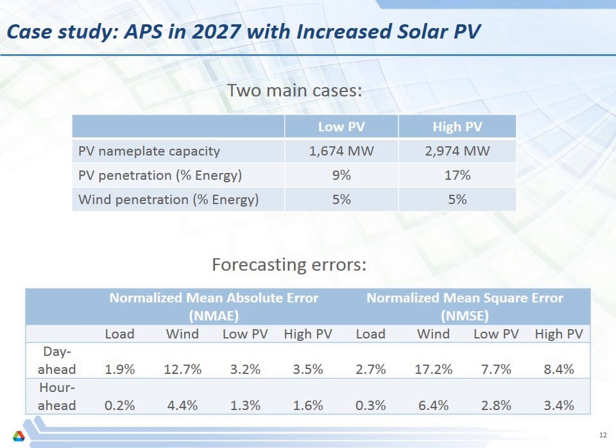Aside from those visibility issues, there actually is a benefit to distributed PV in that it has a broader footprint, so it's more spread out than some of these utility scale plants. The variability we saw from our distributed resources in aggregate was somewhat smaller than what would come from the large 200 megawatt PV plants that we were modeling. So there are two sides to it: the impacts on the distribution system versus the potentially smaller variability from a larger, more spread out footprint. On balance, I can't say which would be easier or harder, but there are trade-offs.